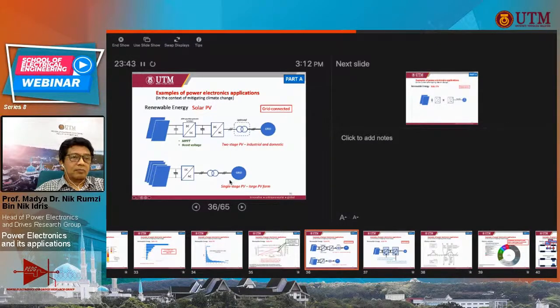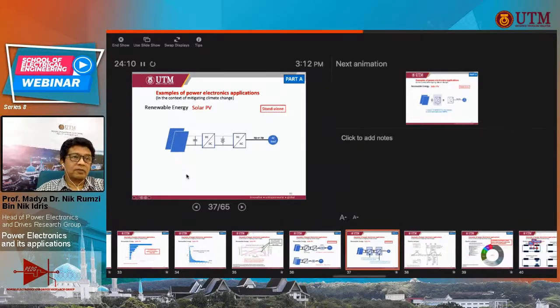Next is the single-stage PV system, typically used for large PV farms, where more PV panels are connected in series, generating enough voltage to be converted to AC and connected to the grid. You don't need to boost the voltage here, and the maximum power point tracking is performed using the DC-AC converter.